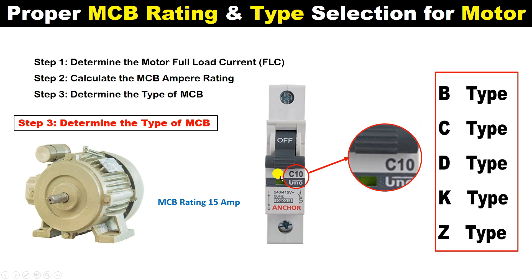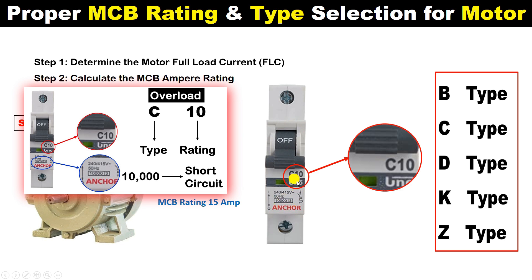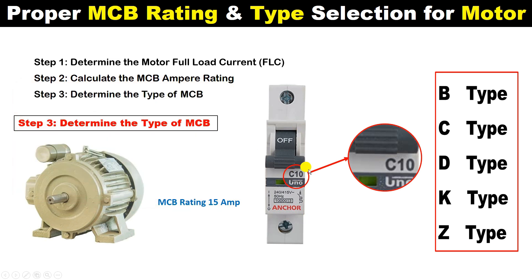If you use an MCB of the wrong type, it will trip again and again or it will never trip, so you have to be careful about the MCB type. Looking at this MCB, you can see it is written C10 — the 10 means the rating of the MCB is 10 ampere, and the C tells you the type. There are 5 types of MCB: B, C, D, K, and Z. All 5 types are used in different places, and the type tells you how quickly the MCB will trip. For a motor, the MCB must be of C type.